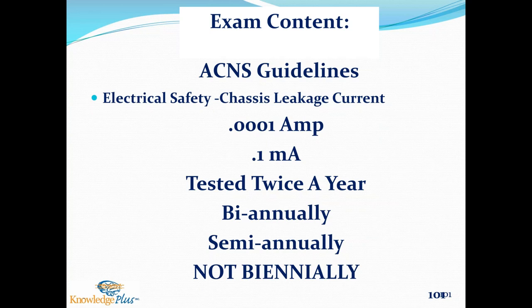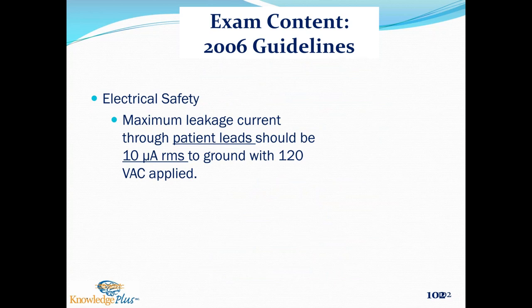The guidelines say it should be tested twice a year. That might also be listed as biannually or semi-annually. Those are synonymous, twice a year. Not biennially, that's every other year. And it's suggested that the electrodes themselves, which are referred to in the guidelines as patient leads, should be 10 microamps RMS.